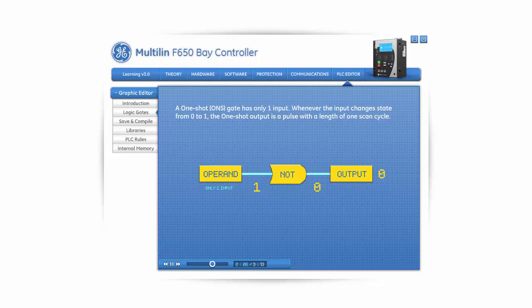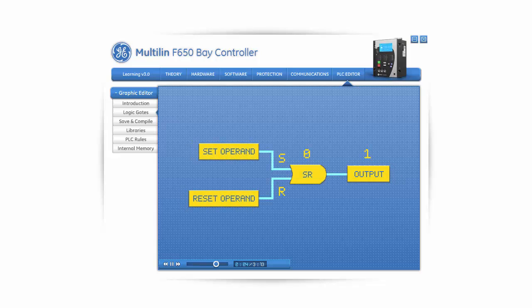A ONE SHOT gate has only one input. Whenever the input changes state from 0 to 1, the ONE SHOT output is a pulse with a length of one scan cycle. A ONE SHOT gate can be inserted by clicking on its icon and clicking again anywhere in the canvas. An SR latch gate, also known as a set-reset gate, accepts two inputs: a set input and a reset input. When the set input has logic state 1, the output is latched to logic state 1, which means it remains at 1 even after the set input changes to 0. The only way to reset the output is if the reset input has a logic state of 1. The SR gate of the F650 is reset dominant — if both the set and reset have a logic state of 1, the reset will dominate and the output will have a logic 0 state.